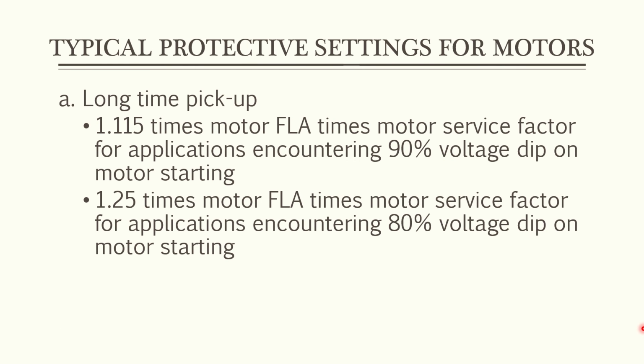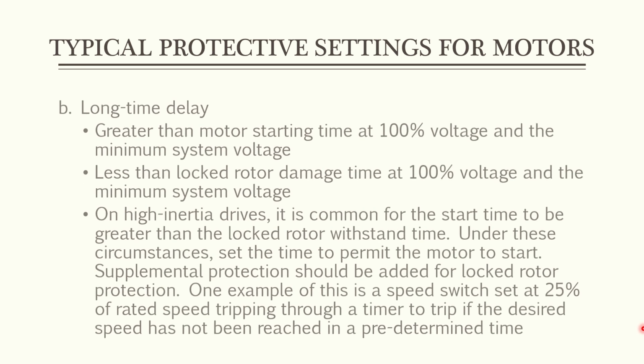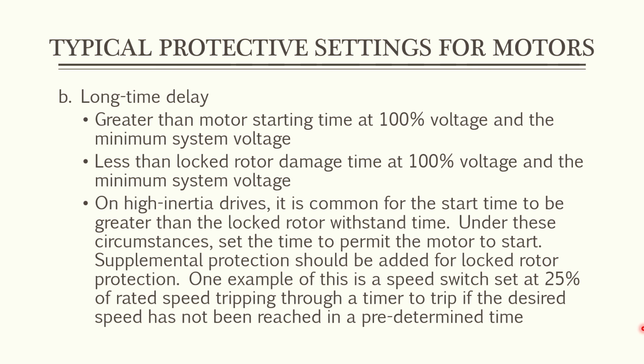Typical protective setting for motor. So first we have this long time pickup. 1.115 times motor full load current times motor service factor for applications encountering 90% voltage dip on motor starting. 1.25 times motor full load current times motor service factor for applications encountering 80% voltage dip on motor starting. Next we have long time delay. Greater than motor starting time at 100% voltage and the minimum system voltage, less than locked rotor damage time at 100% voltage and the minimum system voltage.